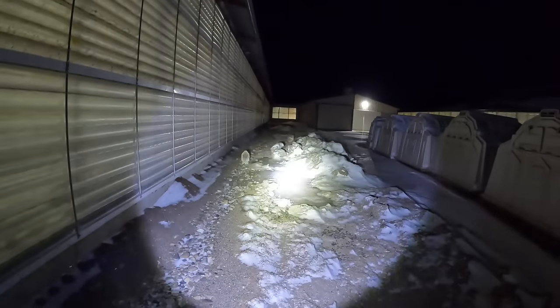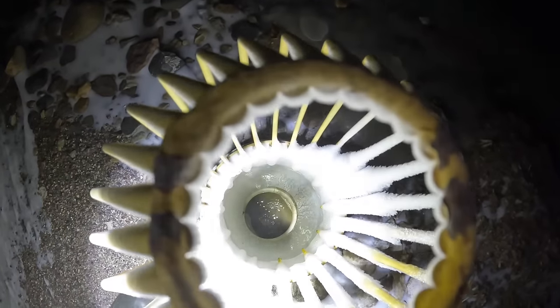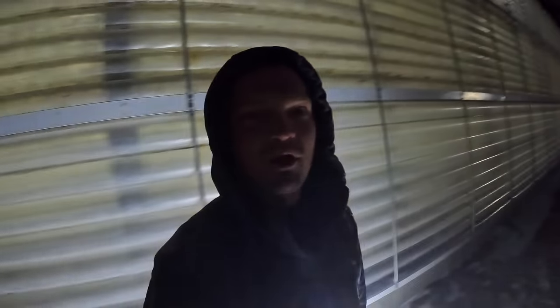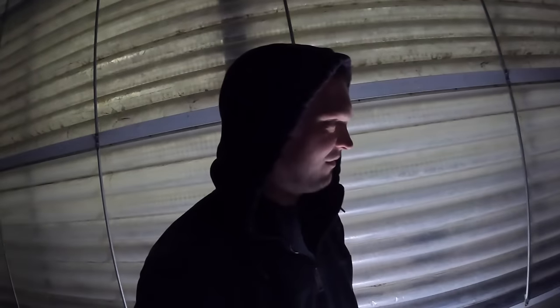And I noticed this little spot of water that I did not see yesterday, and there is steam coming out of this riser. So I walked over here and I can already hear water running.